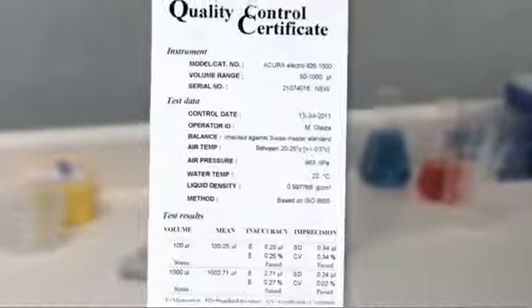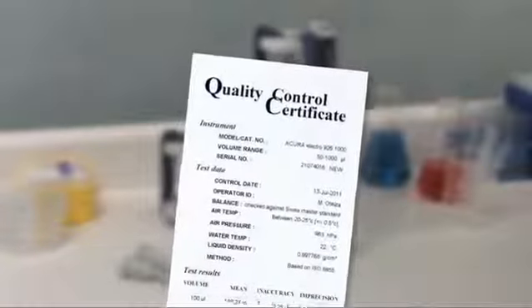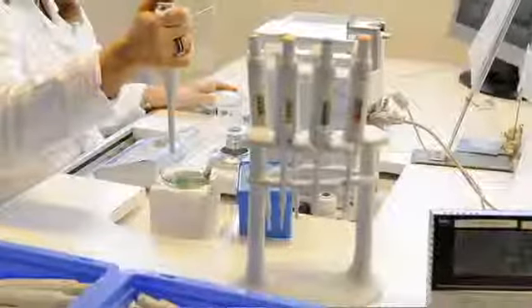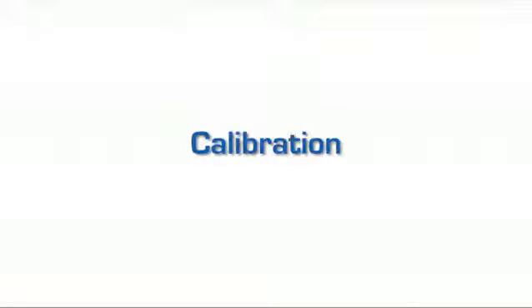Each Acura Electro pipette is factory tested for conformity, according to ISO 8655 standards. To proceed, finish the pipetting sequence. Select the desired pipetting mode, perform 10 measurements on an analytical balance, and compare results with the recommended performance from the supplier or internal procedures. Determine the need for the new calibration and the number of calibration units to add or retrieve. Instrument software gives immediate access to the calibration menu. The new settings are entered directly into the keyboard.